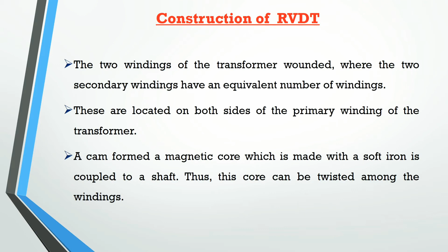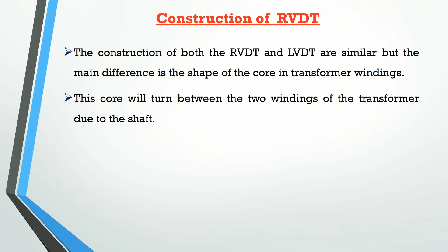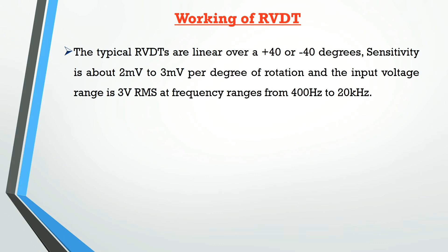The construction of both the RVDT and LVDT are similar, but the main difference is the shape of the core in the transformer windings. This core will turn between the two windings of the transformer due to the shaft. Now let us see the working of RVDT. The typical RVDTs are linear over plus 40 or minus 40 degrees. Sensitivity is about 2 mV to 3 mV per degree of rotation, and the input voltage is 3 volt RMS at a frequency ranging from 400 Hz to 20 kHz.